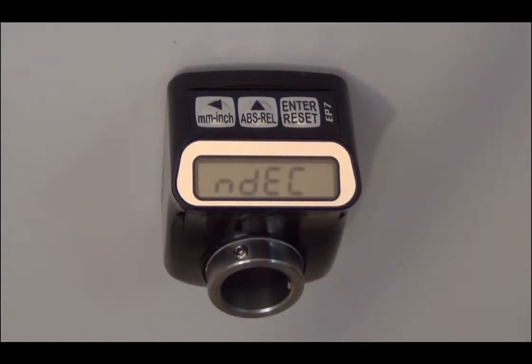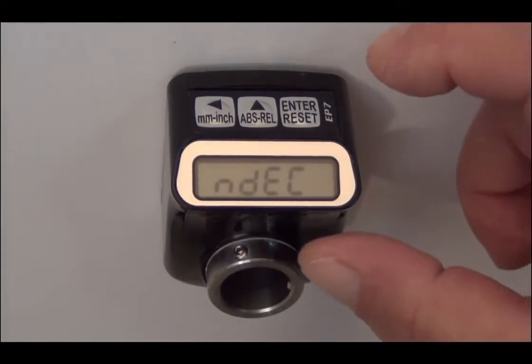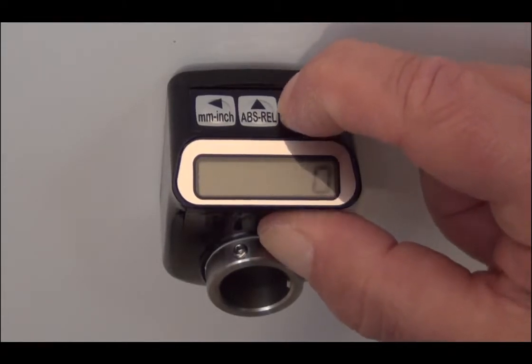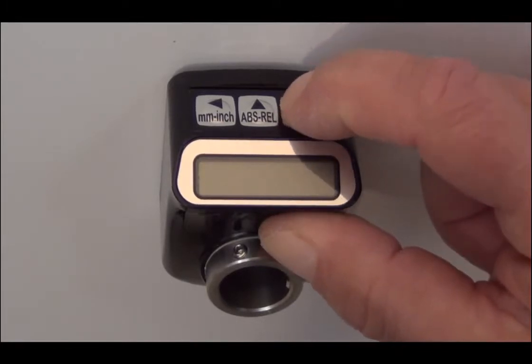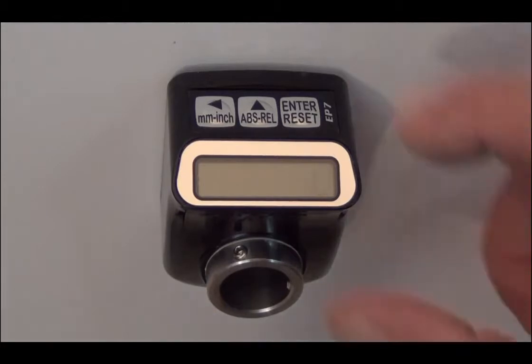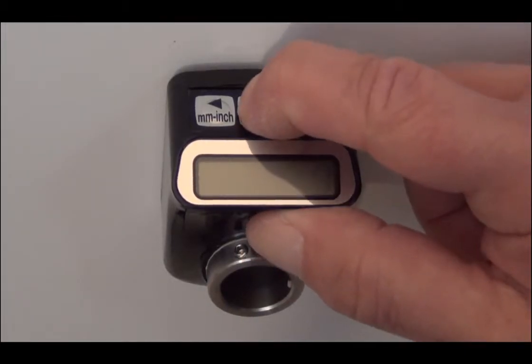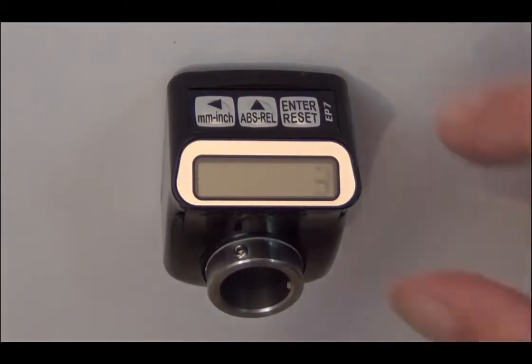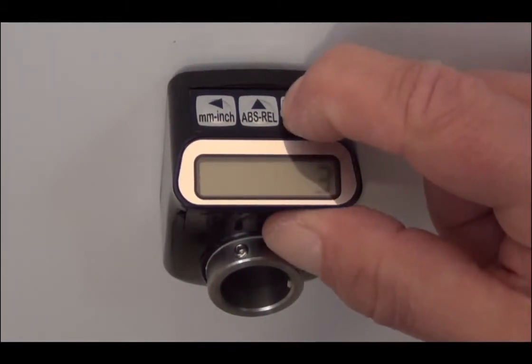NDEC is now displayed, which is the number of decimal places that the display will display with the desired COUNT PER TURN. In this example, we wish to display thousandths of an inch, so three decimal points will be programmed. Depress the ENTER key until the number of decimals desired is flashing, and then depress the COUNT key UP until 3 is displayed. Then hit ENTER.